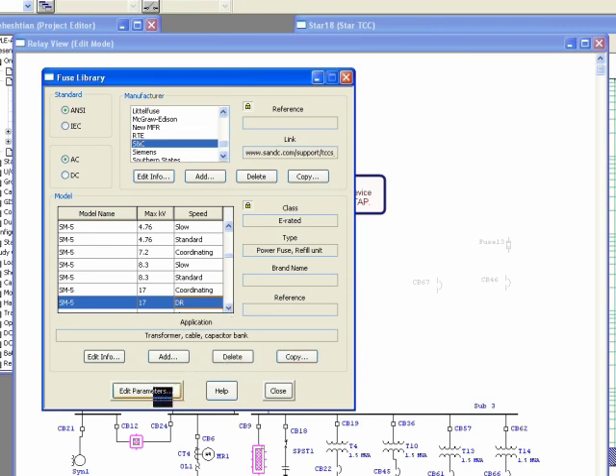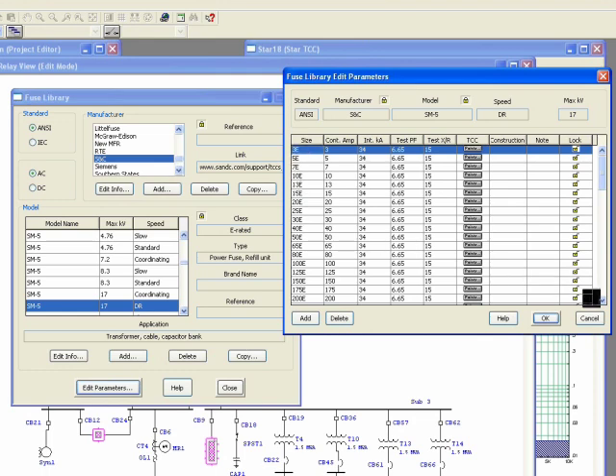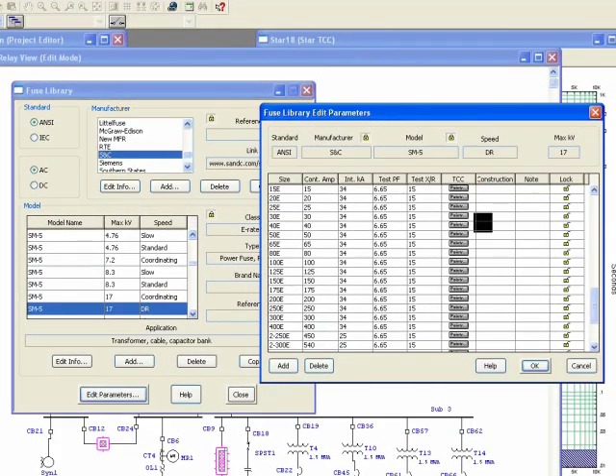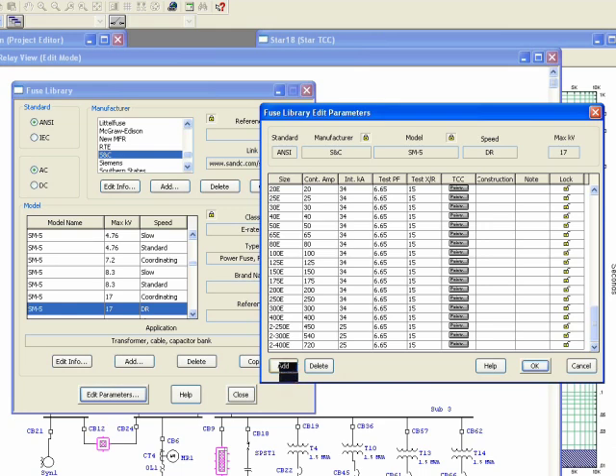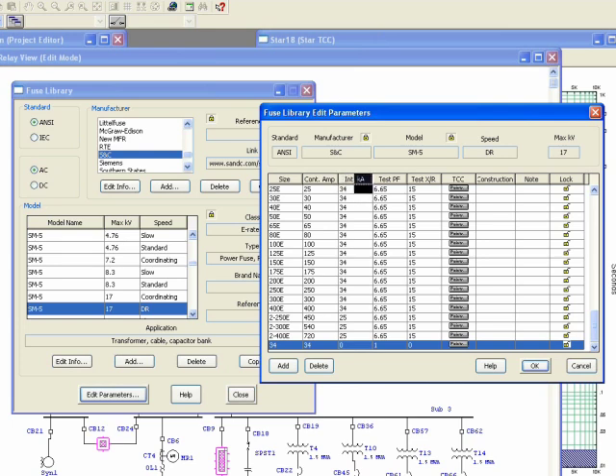The next function is 'Edit Parameters,' which allows you to change sizes or add new sizes under a model. Click 'Edit Parameter' and a window opens showing all available sizes. To add a new size, click on a row, specify the size ID (for example, 34), the actual continuous amp rating, and then the interrupting kA. In ANSI standard this is called interrupting kilo amp; in IEC it is called breaking rating — they refer to the same field.